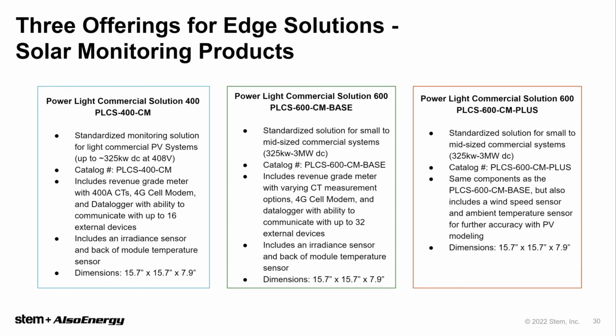And what's great with the PLCS 600 is even though it's just as plug and play as the 400, we do have a lot more customization ability with it, because it doesn't come with a standardized set of CTs. So we could have 600 amp CTs on it, we could have split core 2000 amp CTs on it, and that really allows us to have this device work on larger systems. And we usually see it going up to 3 megawatts where this SKU works very well. With this solution, we also have the ability to communicate to a few more devices, up to 32. So that's including your inverters and weather stations and sometimes even trackers, things like that.